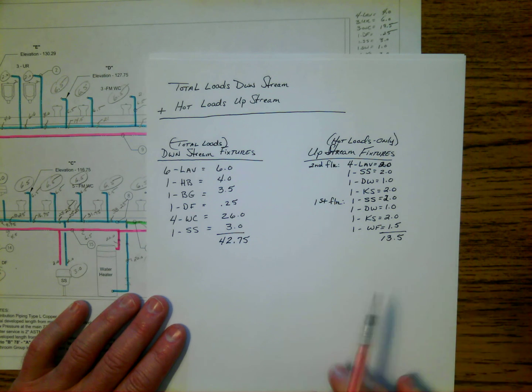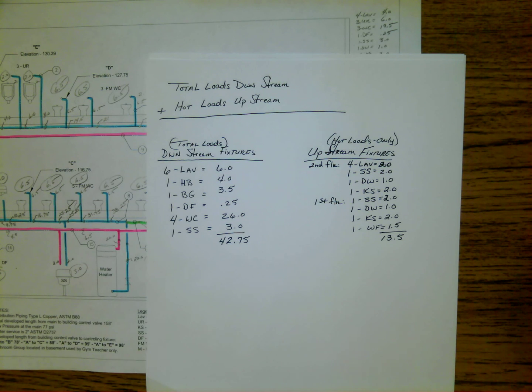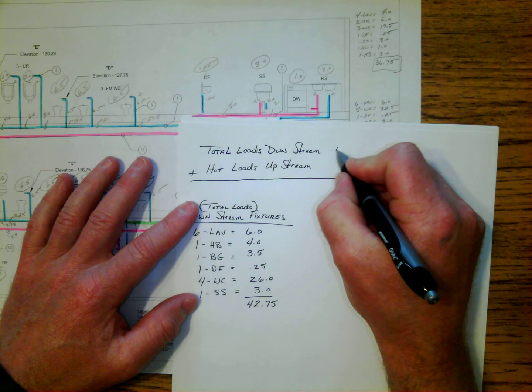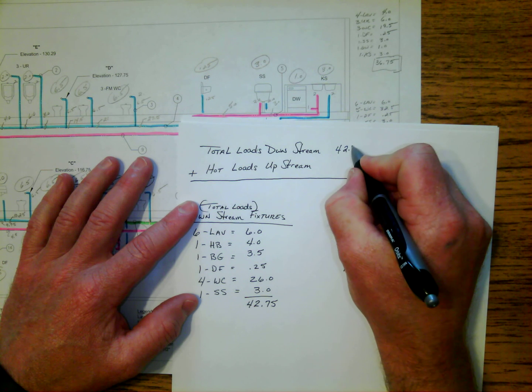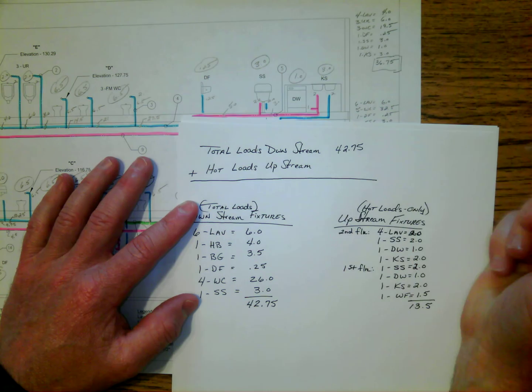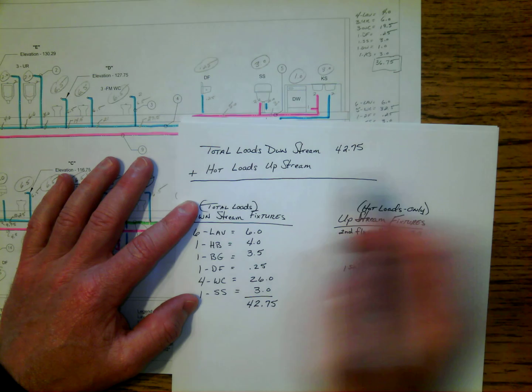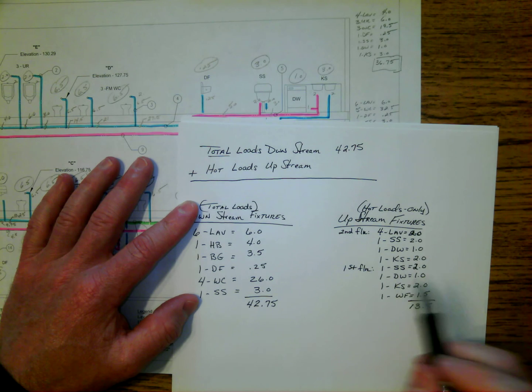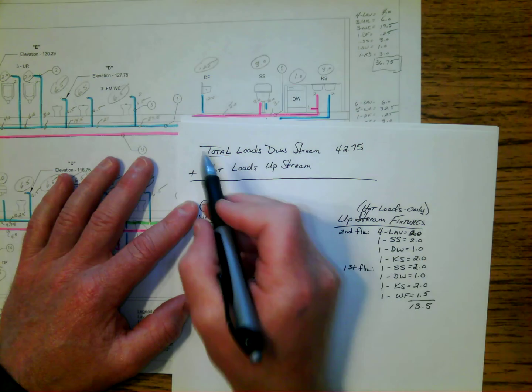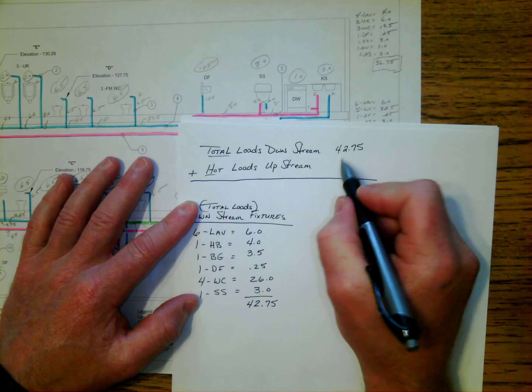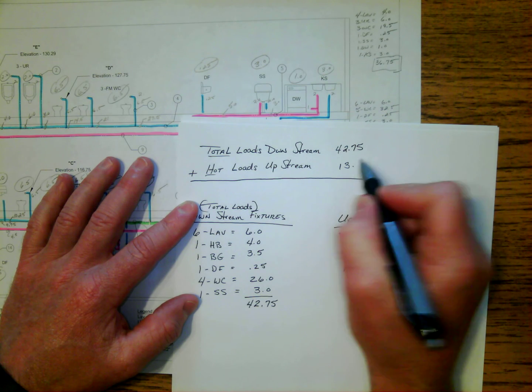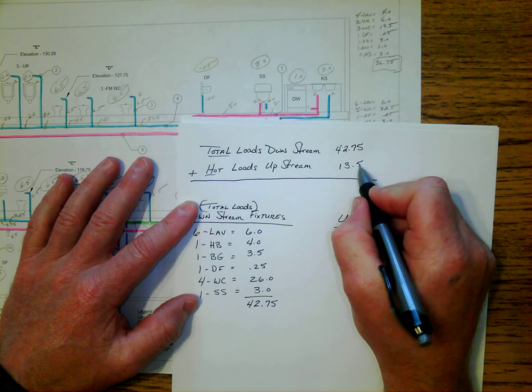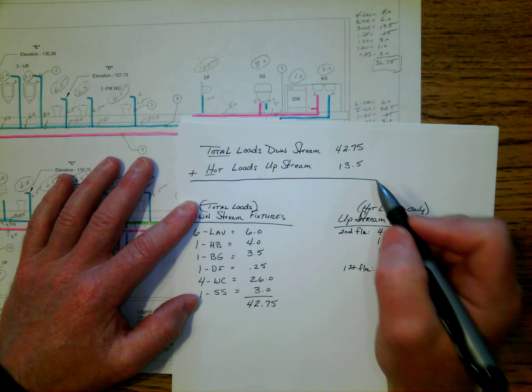So now, knowing that, we can take those two numbers, the 42.75 WSFU, which was the total load of those fixtures downstream, plus the hot loads that we just looked at, which was 13.5. And when we add those two together, we end up getting 56.25.